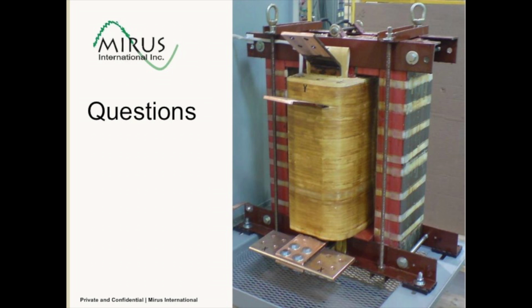I believe this is our last question. How do you address existing NGRs on the generators? Good question. A lot of times NGRs are used to intentionally limit the fault level of the power system. So if the fault level is too high and it's difficult or expensive to provide protection, circuit breakers, and other protection systems for that generator system, then NGRs can be installed to provide either a high resistance grounding system or a low resistance grounding system, and now they're even looking at hybrid grounding systems, which are combinations of a low resistance and a high resistance. In those scenarios, you want the resistor in the circuit to limit the fault current.